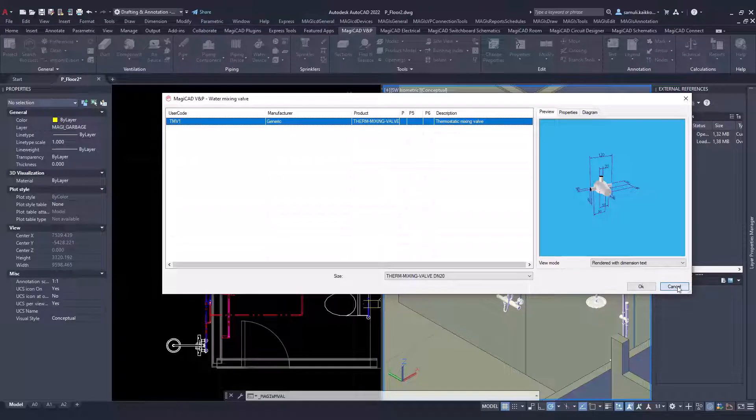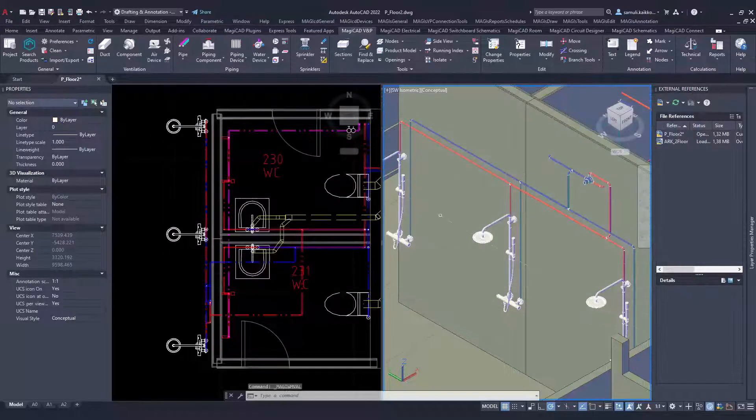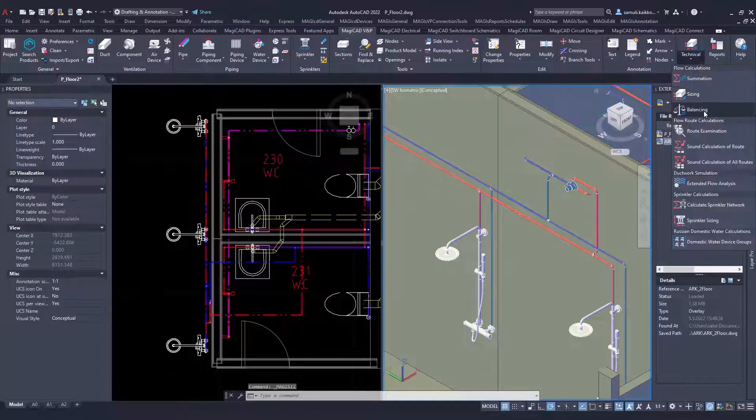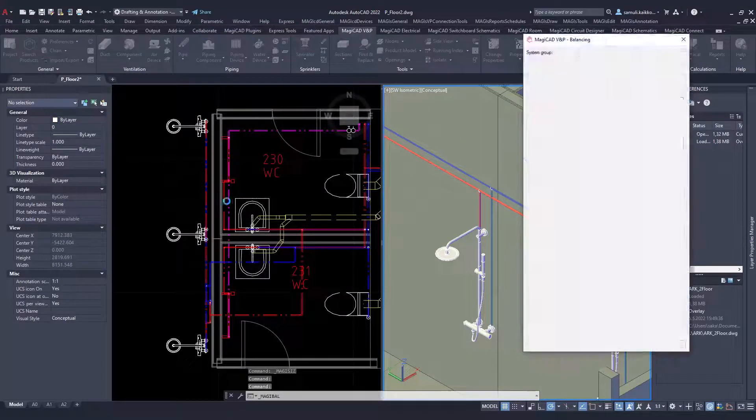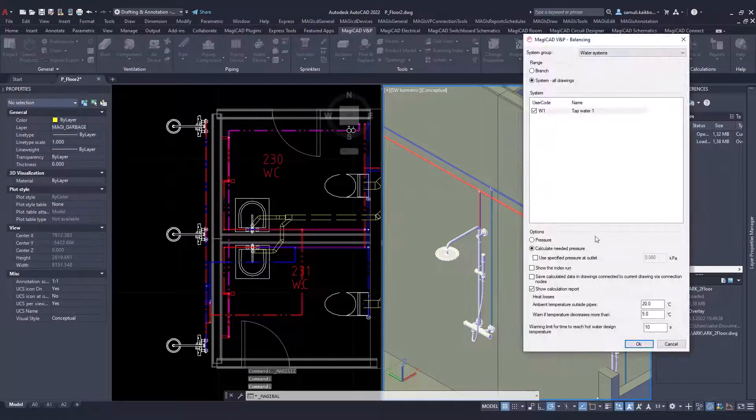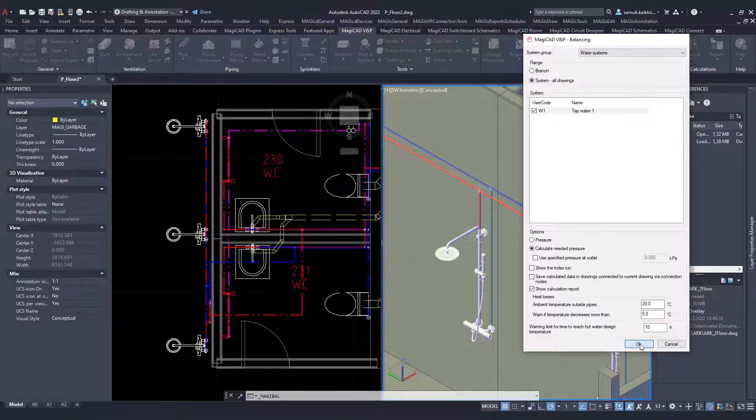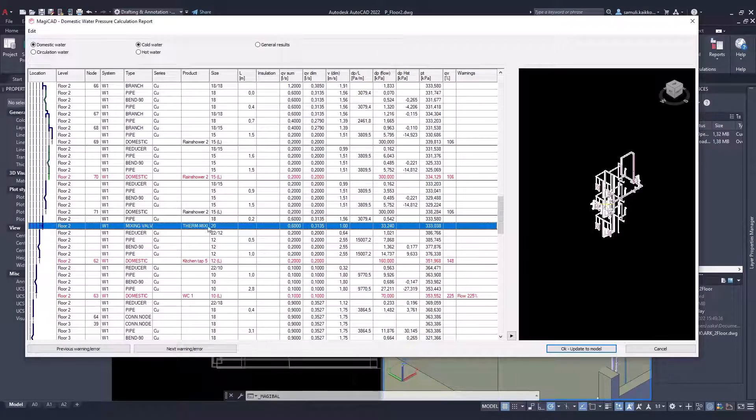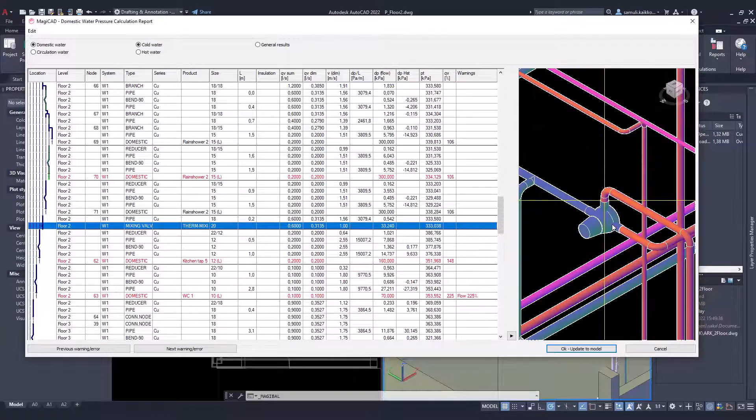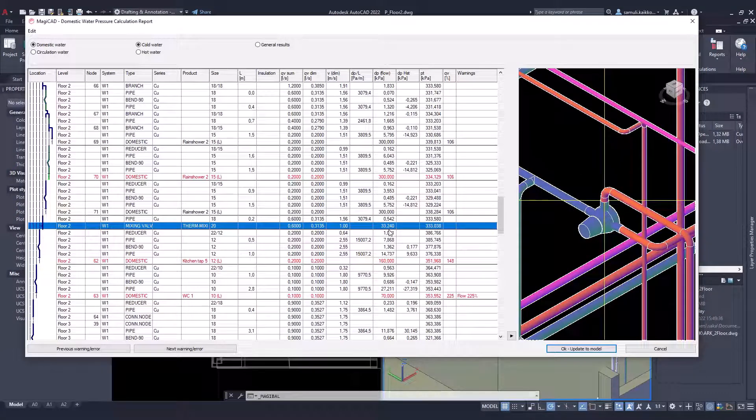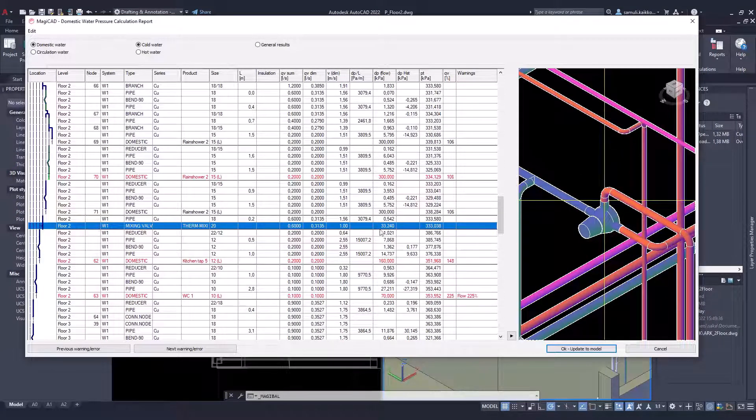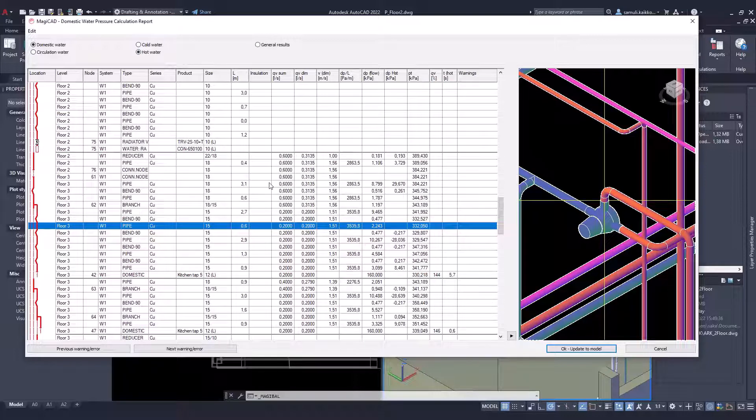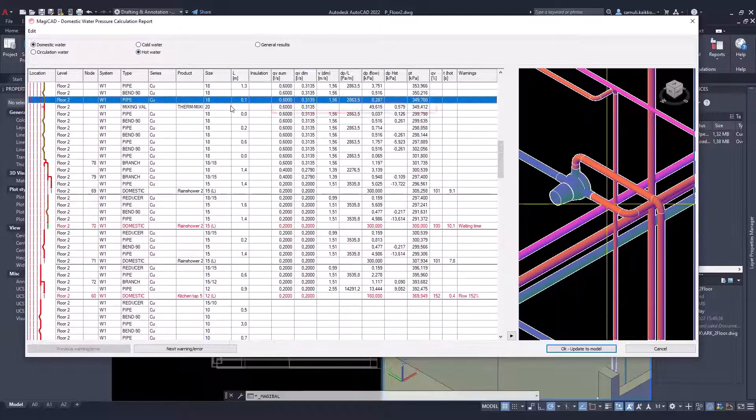Let's perform some calculations. Sizing calculations ensures that pressure drop or flow parameter is inside the defined limits. Therefore mixing valve is also taken into account. In my example I skipped the sizing and performed balancing directly. As you can see all pressure drop values are calculated correctly. Both in hot water side and in cold water side.